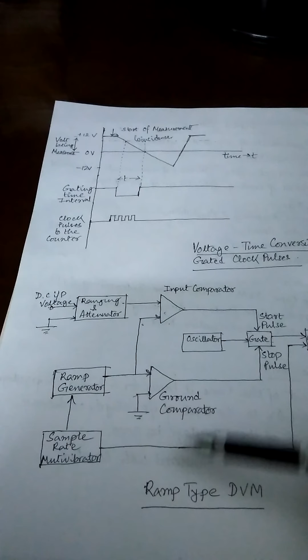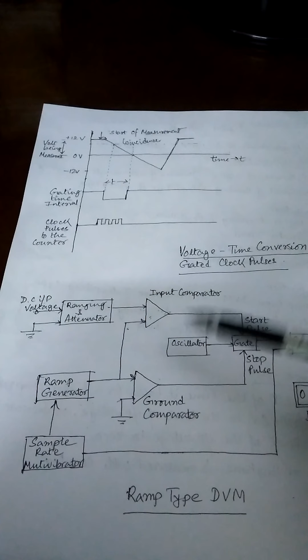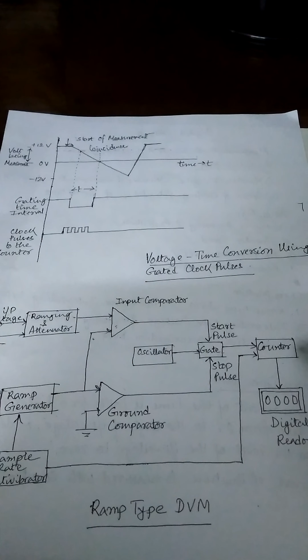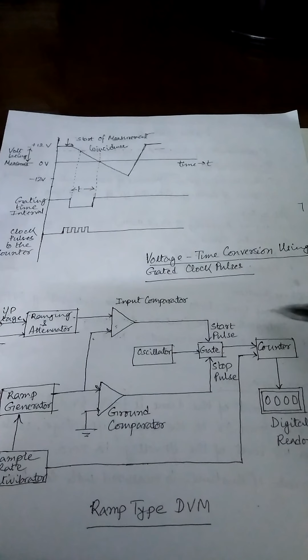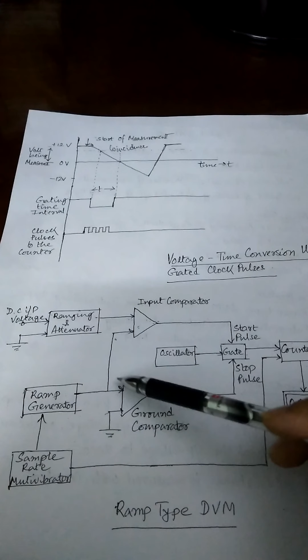And this sample rate multivibrator has another function here. After the gate is in disabled condition and the total cycle is over, for the next cycle the sample rate multivibrator initiates the ramp generator to start the ramp voltage, and at that time a reset pulse is also applied, and the counters and the others also go to their initial value, that means 0. Only then is the next pulse from the ramp generator provided here.